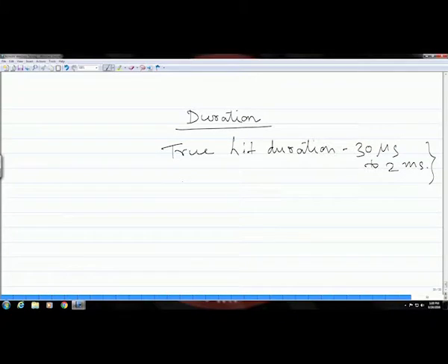and that is what we are going to see now. So, you first collect the hits or the emission signals and then plot them as a function of the amplitude. So, the data will be in terms of the duration, as I said, that is the parameter that we are going to use, and you plot it as a function of the amplitude. Okay. So, if you keep getting acoustic emission signals from a particular source, that signal will increase over time in size and in strength.